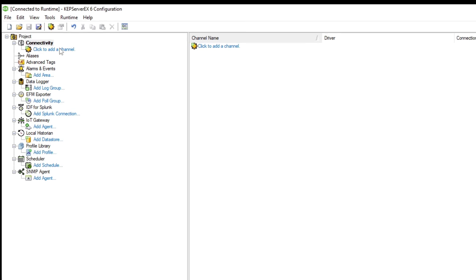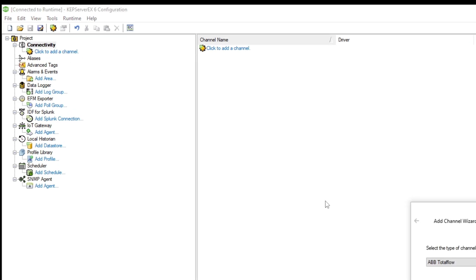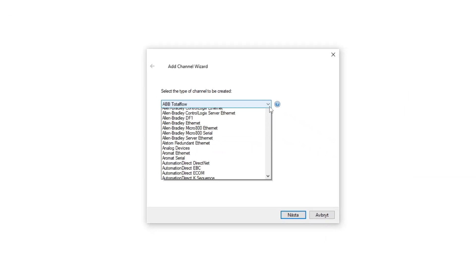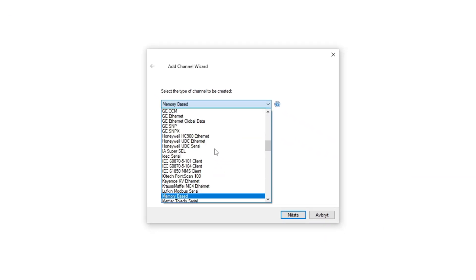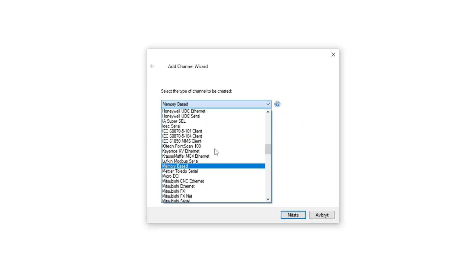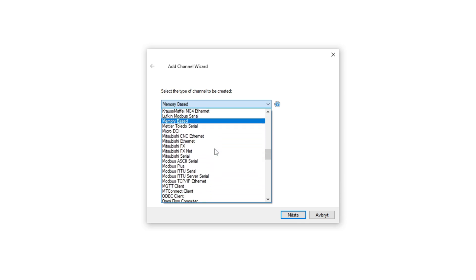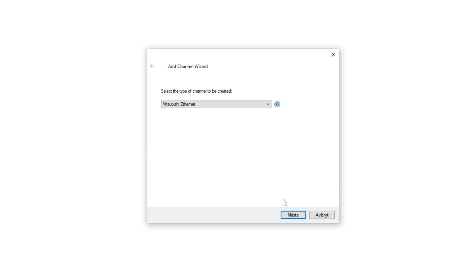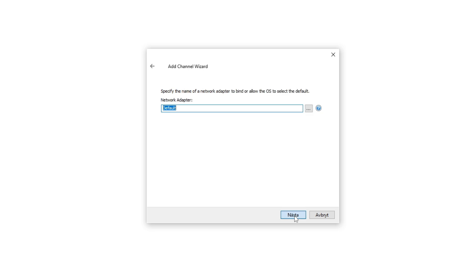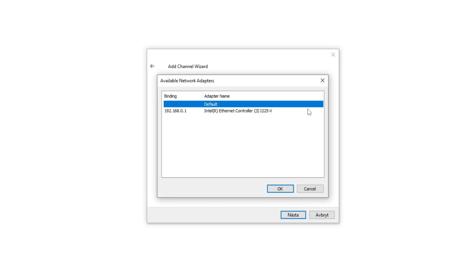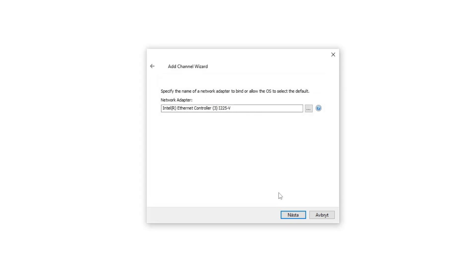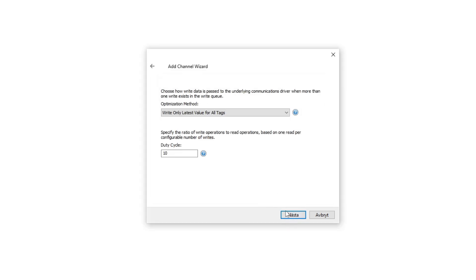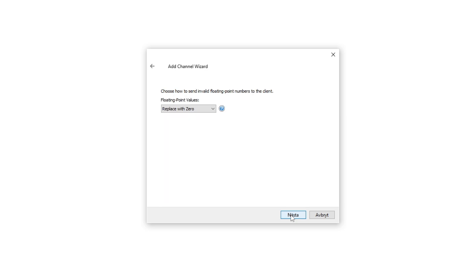In Kepware we want to add a channel. Since I am connected via Ethernet, I will choose Mitsubishi Ethernet. As the network adapter, we want to choose the computer's network card. Be sure that your IP address on your computer is in the same subnet range as the PLC, else they won't be able to communicate.